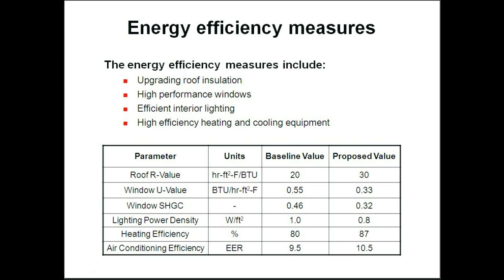The energy efficiency measures, which will establish our proposed building values, are going to be: upgrading roof insulation, establishing high-performance windows, efficient interior lighting, and high-efficiency heating and cooling equipment. In order to model those upgrades, we're going to change the roof R-value from 20 to 30. The window U-value will decrease from 0.55 to 0.33, and the window solar heat gain coefficient will likewise decrease to 0.32. The lighting power density will decrease by 20% to 0.8 watts per square foot. We're using condensing boilers now, so instead of 80% efficiency, we've jumped to 87%. Purchasing high-efficiency cooling equipment results in an EER of 10.5, up from 9.5. Here we see the new input values, which were acquired by adjusting the roof R-value, window U-value, etc., to the new values.